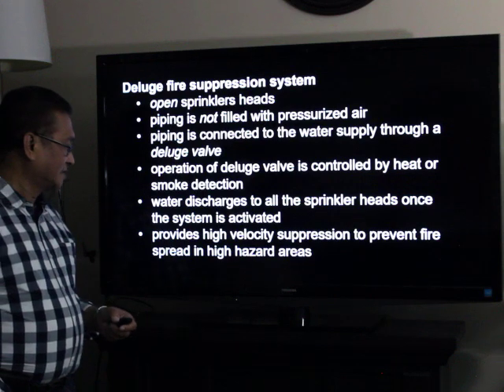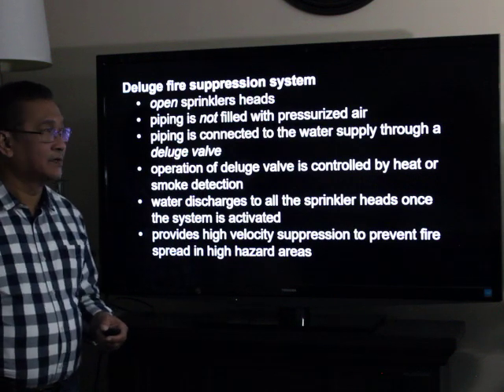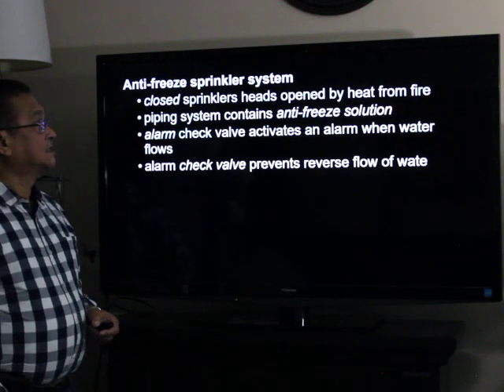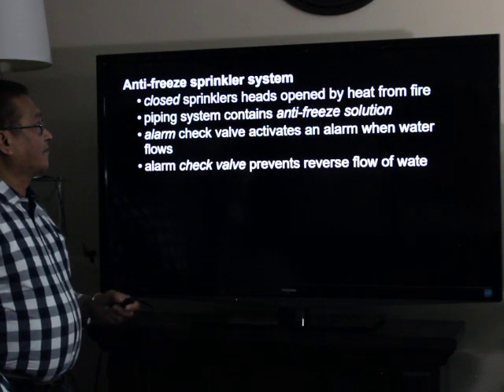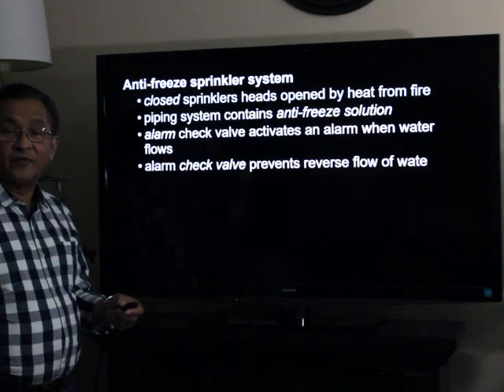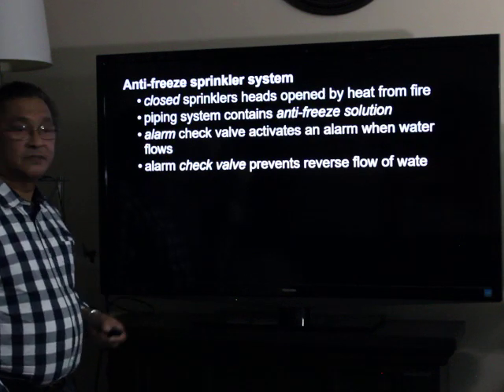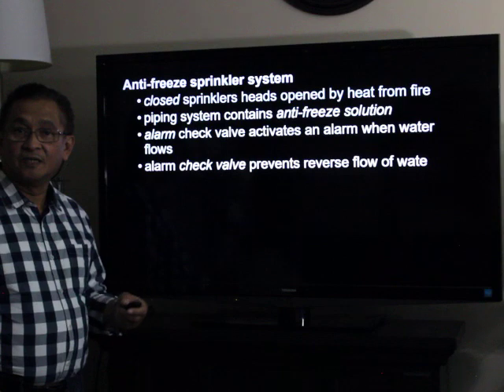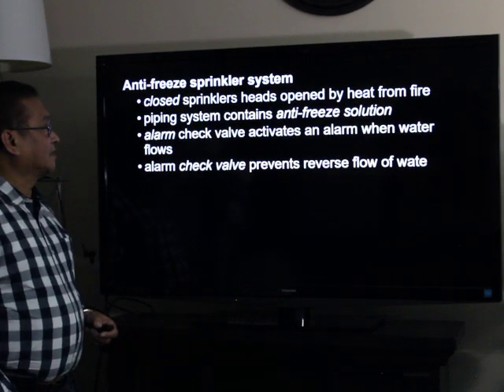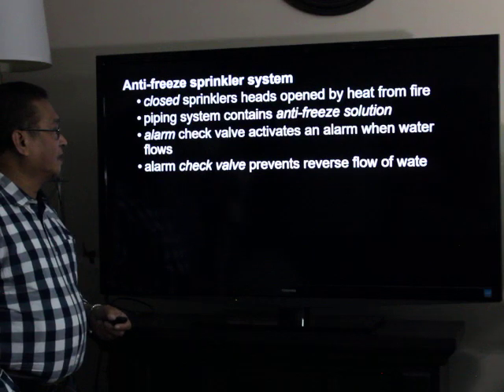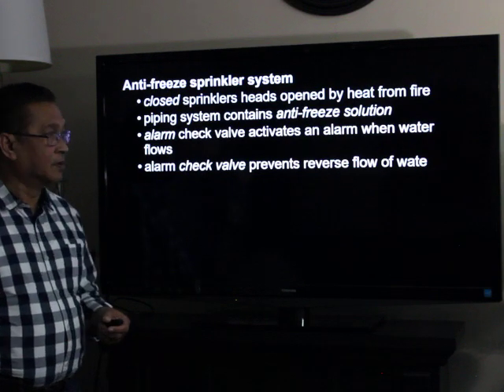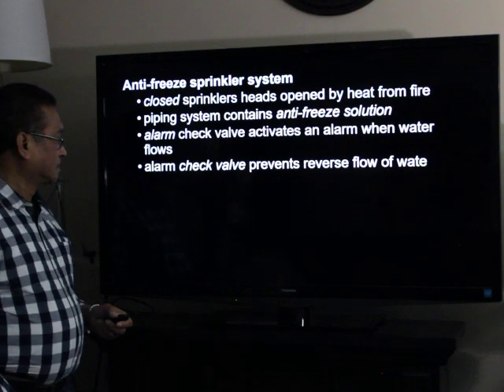To prevent fire spread in high-hazard areas. The last one is the anti-freeze sprinkler system. We have closed sprinkler heads opened by heat from a fire. The piping system contains an anti-freeze solution like a glycol solution. The alarm check valve activates an alarm when water flows and prevents reverse flow of water.